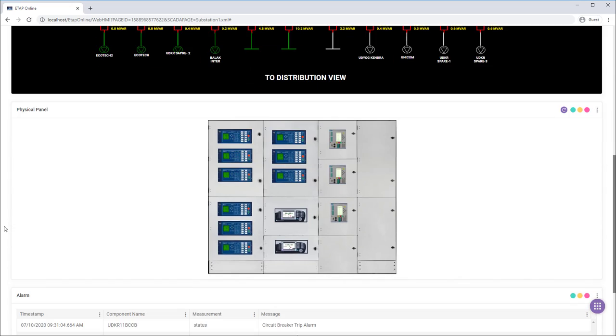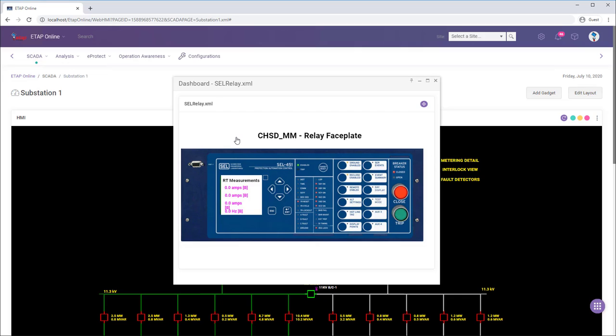We are currently looking at the electrical network, but now let's look at the physical representation. The physical twin includes the representation of the panels as they are constructed, including nameplates. These faceplates contain real-time data, indicators, and you can also send commands from the faceplates, so you can open and close from this relay itself. These faceplates are templatized, so you can pull from an existing template or create a new one to use for a specific relay model.